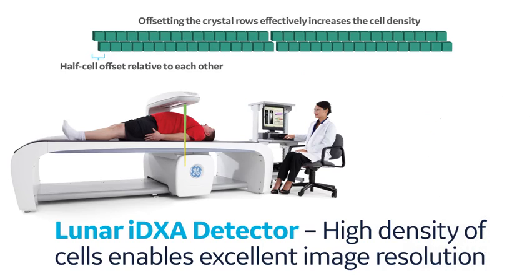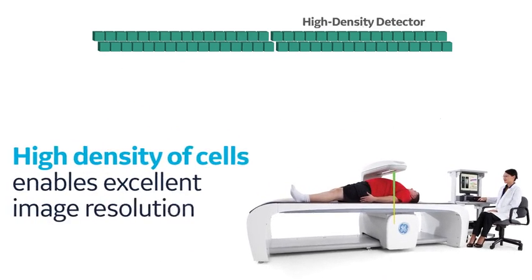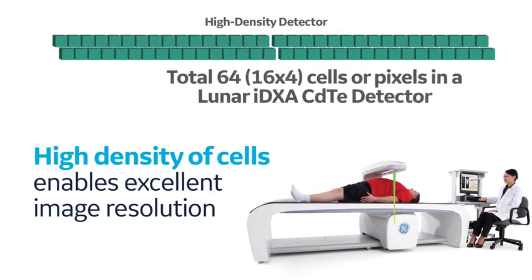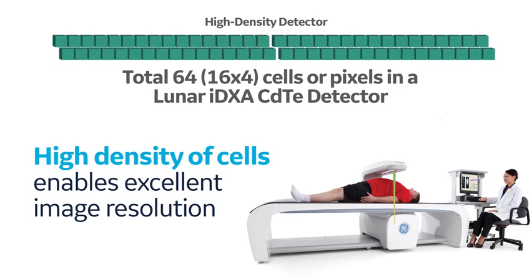Offsetting the crystal rows effectively increases the cell density while simultaneously maintaining high x-ray flux in each cell. Image quality improves with high density of cells and sufficient x-ray flux per cell in the crystal. The fundamental reason behind the excellent image quality of Lunar iDXA is its high density of cells in the crystal combined with sufficient x-ray flux.